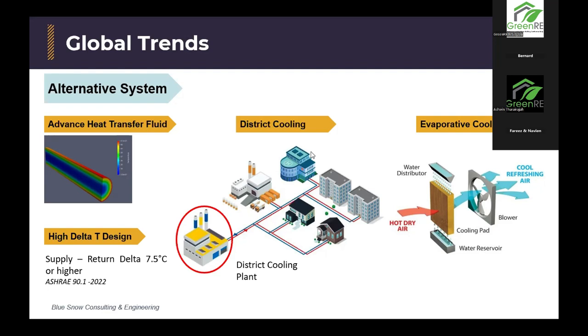Then you have a high delta T design. This is a chilled water requirement. Normally chilled water is designed for a 6 degree difference between the supply and return temperature of the water, the delta difference. Having a high delta T is good because you can reduce your pump size and your pump consumption. So overall, you get a net positive in terms of energy consumption as a plant.